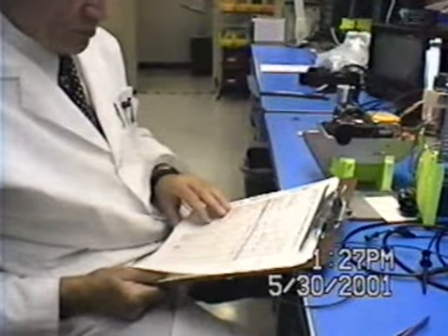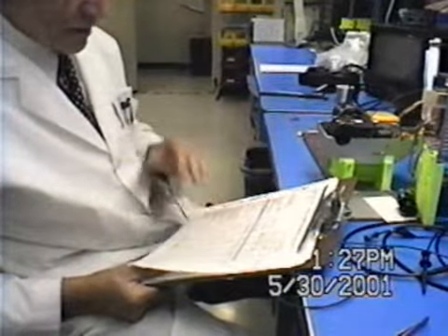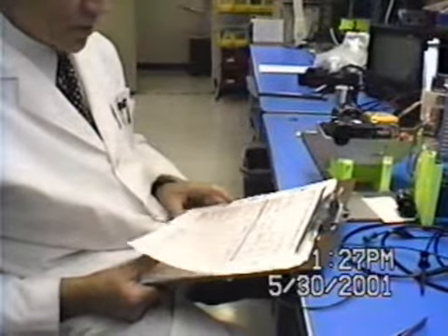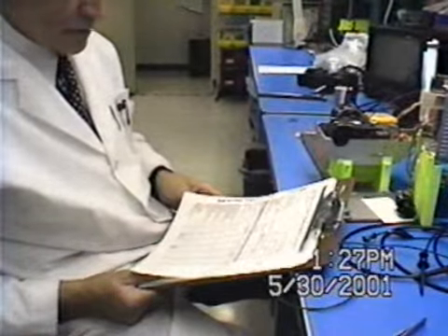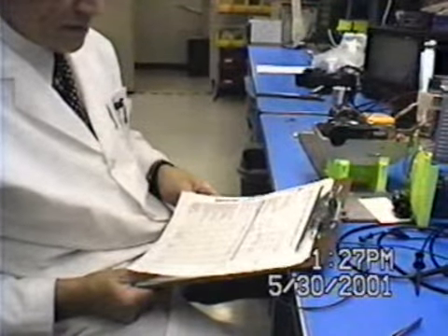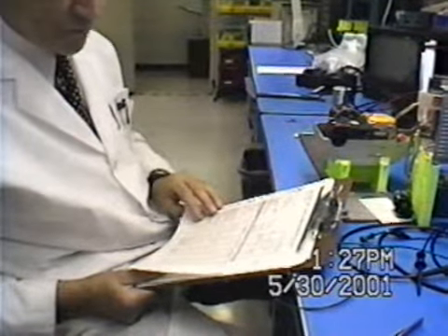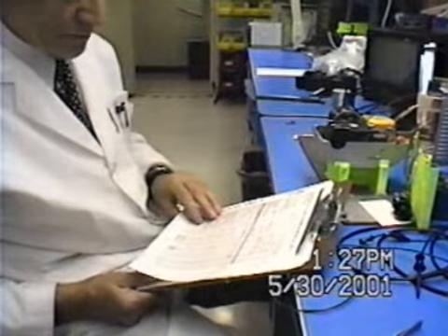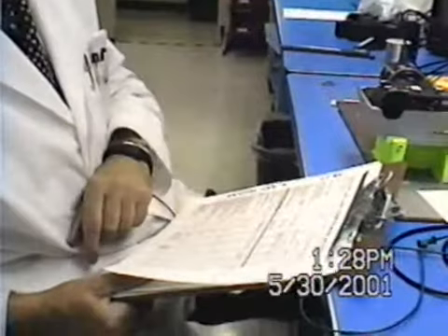What we did is we changed resistor R109, which is part of the voltage divider on the F board, just ahead of the second AC amp.